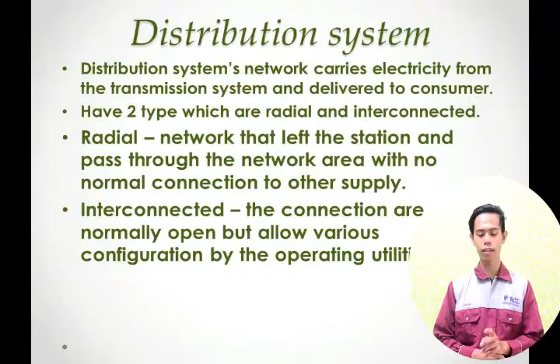An interconnected network is generally found in more urban areas and has multiple connections to other points of supply. These points of connection are normally open but allow various configurations by the operating utility through closing and opening switches.